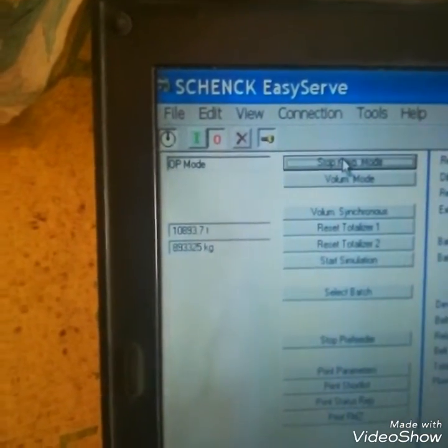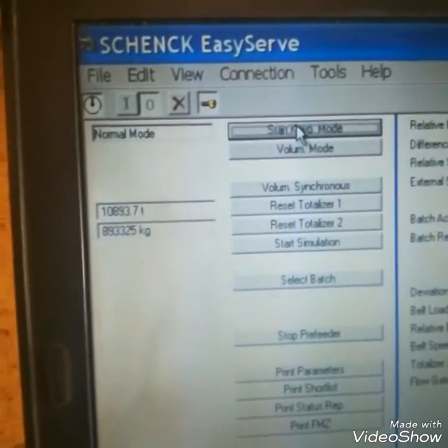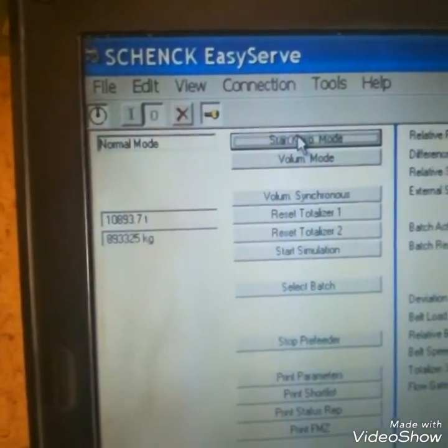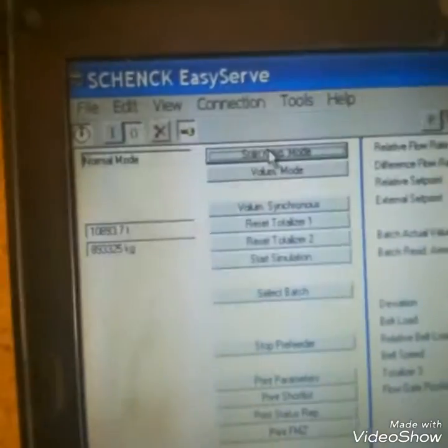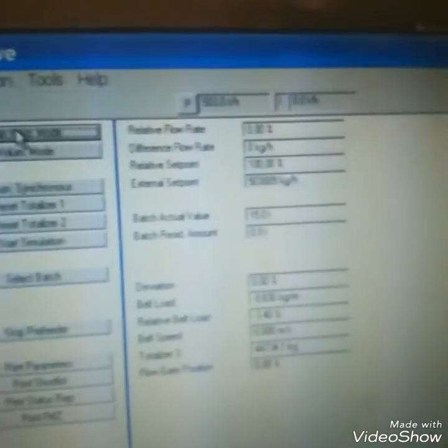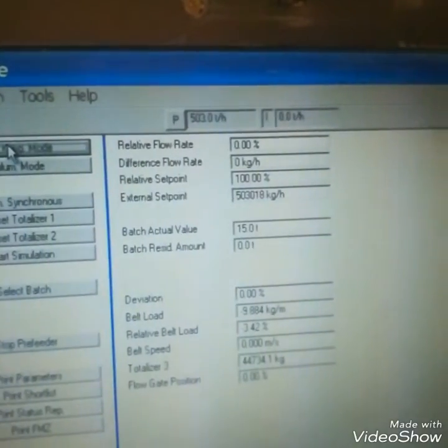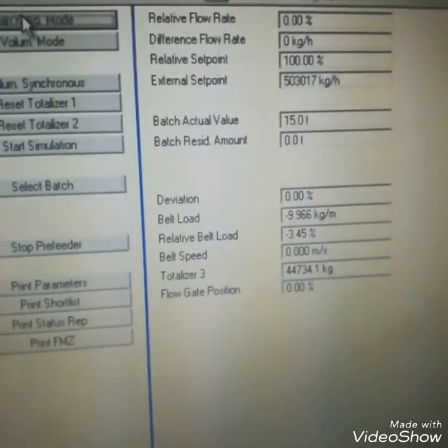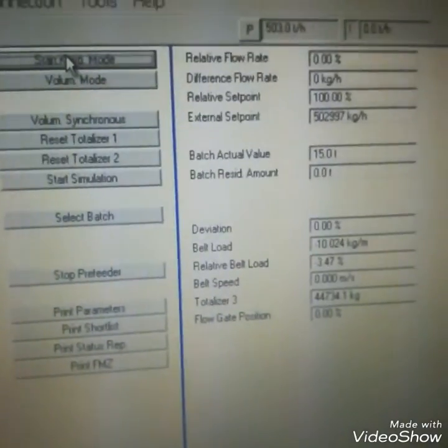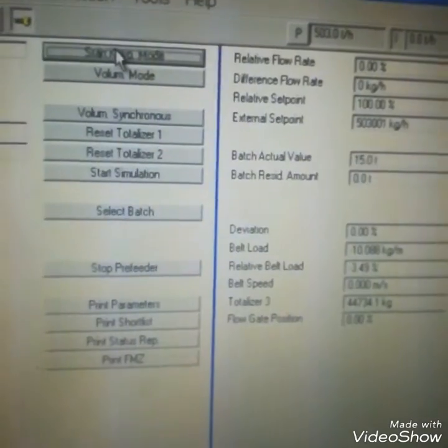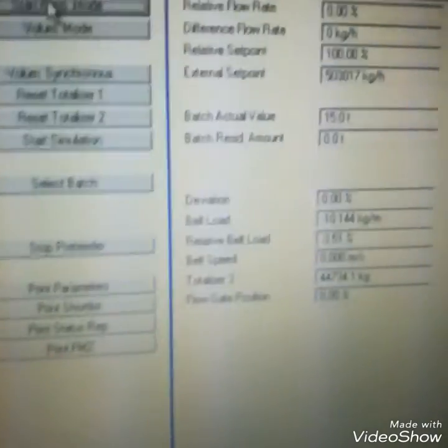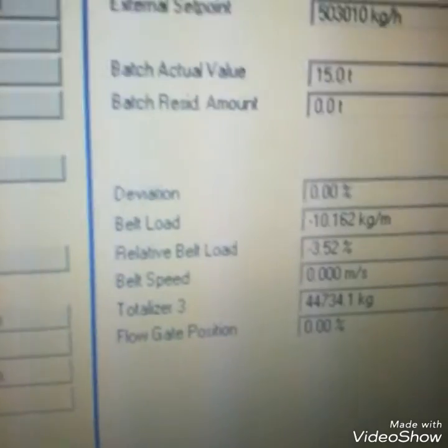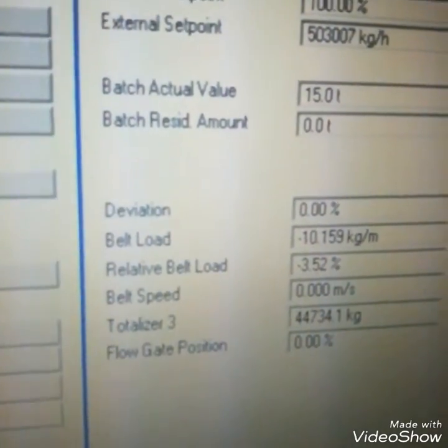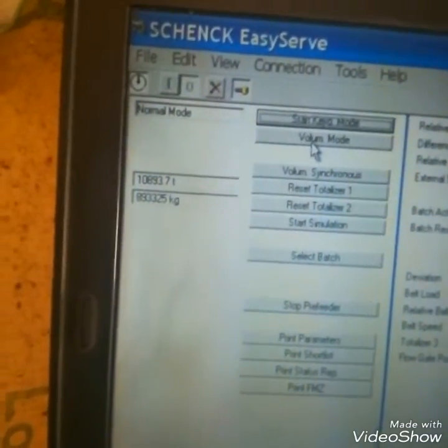Now I can change its mode. Now it's in the normal mode. In the normal mode, this weigh feeder will be started from the CCR and it will follow the set point from the CCR. So I have just operated this weigh feeder from this laptop through this software EasyServe 1.1. You can see now belt is stopped, its speed is 0 and it's showing a little weight.